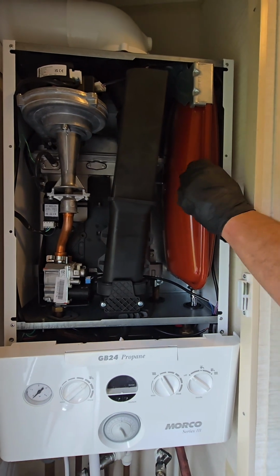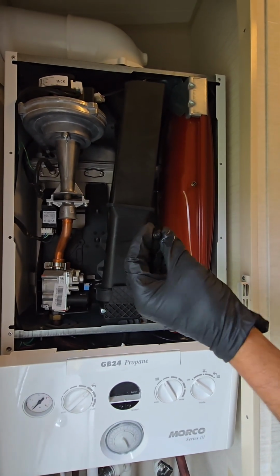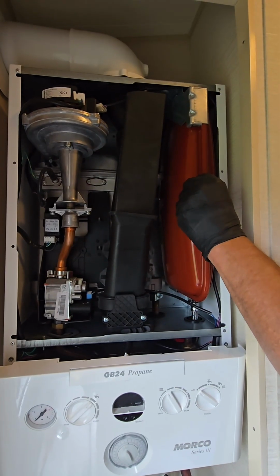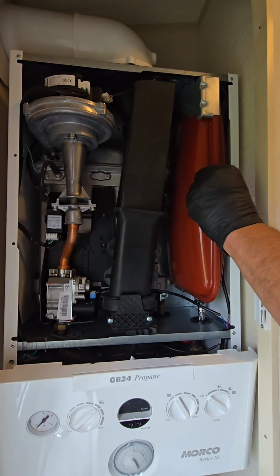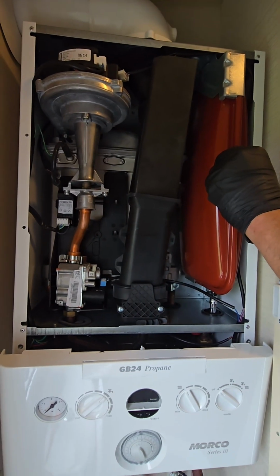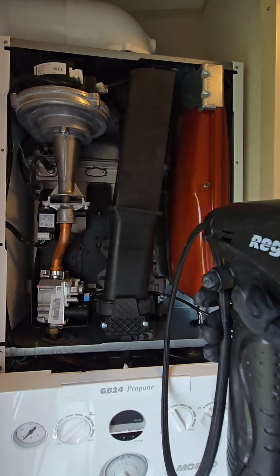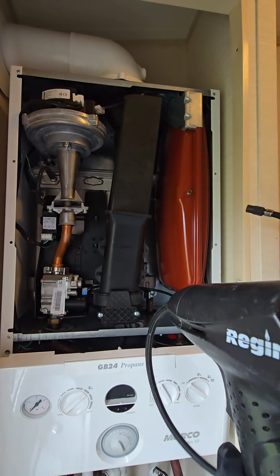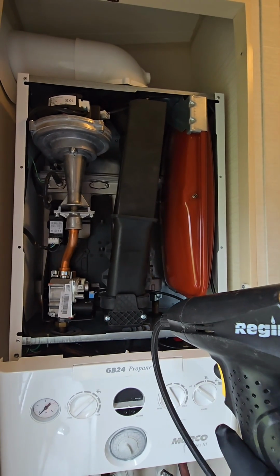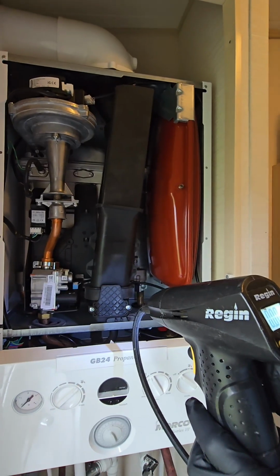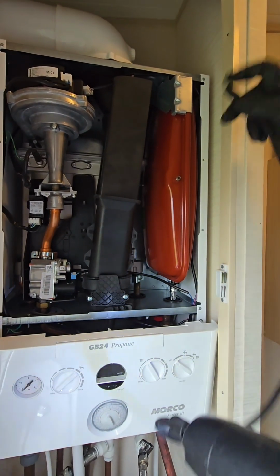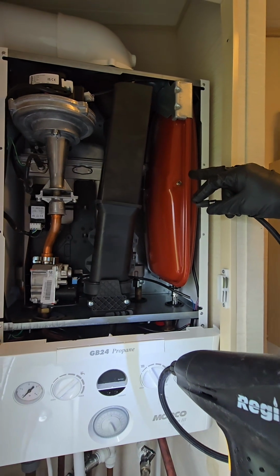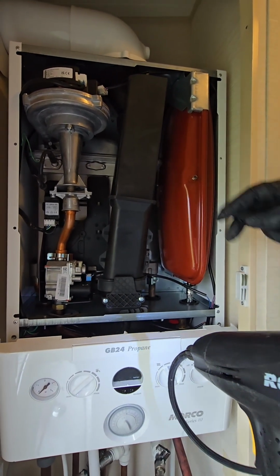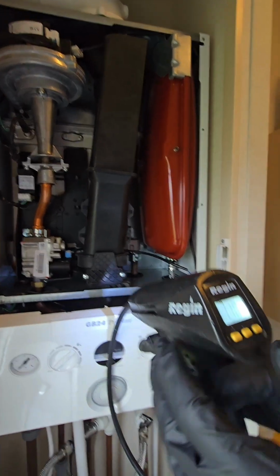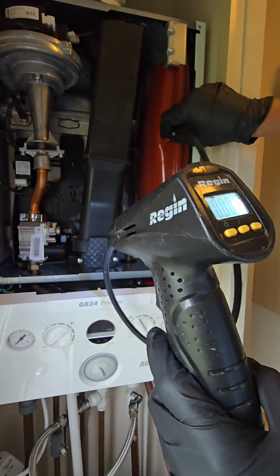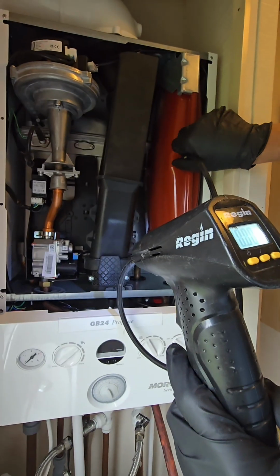So remove the Schrader valve cap, use the back part of the cap to press in the Schrader valve and fully deflate the vessel. Right, so I'm going to use the Regin vessel jet, however a stirrup pump or any other pump would suffice. Different manufacturers have different pressure settings for the vessels, however we just base it all on 1 bar, so we would then set it to 1.1 bar, as when you take it off you will lose a bit of pressure.